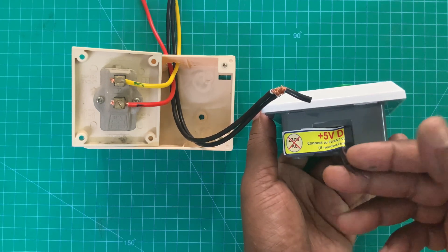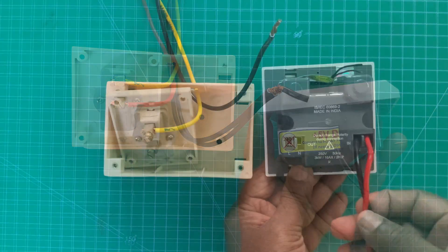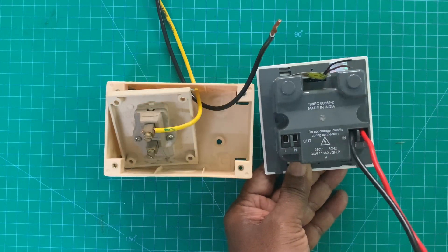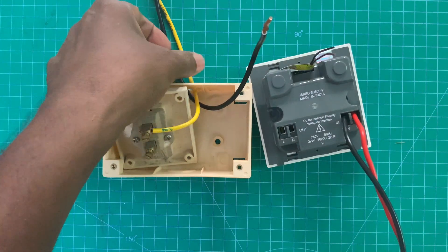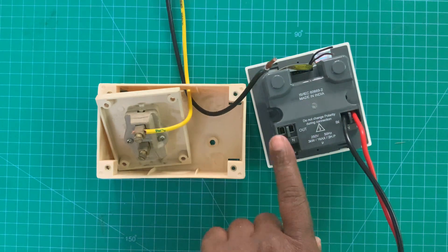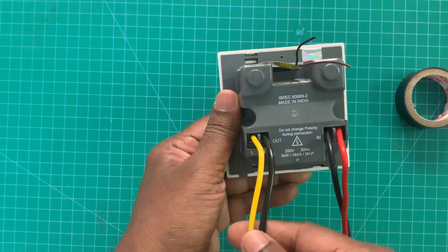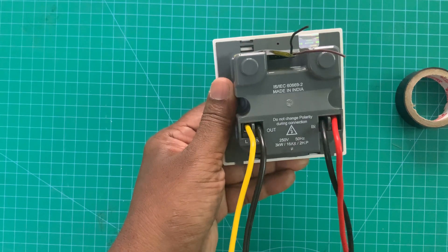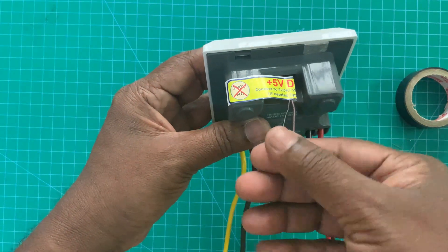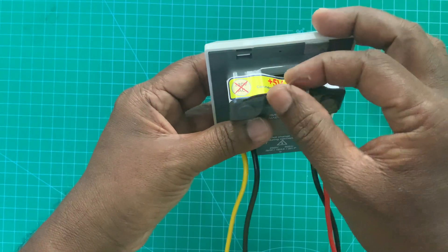If you have a float switch, connect to these two wires. I have removed the incoming wire from the voltage switch and connected it to the Svigo. Now I am going to remove the outgoing motor wire and connect it to the output of the Svigo. Two motor wires are now connected to the Svigo output. I don't have a float switch, so I keep these two wires idle.